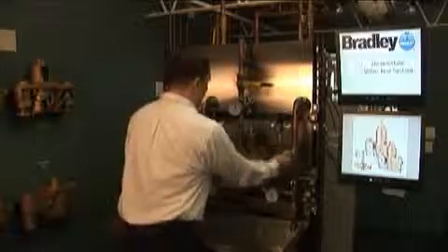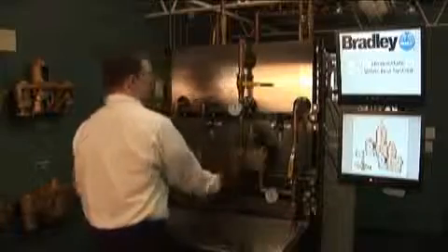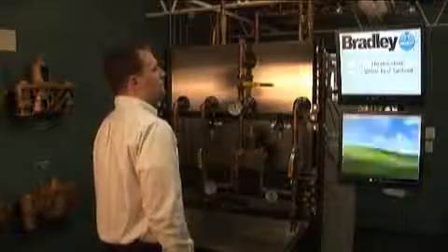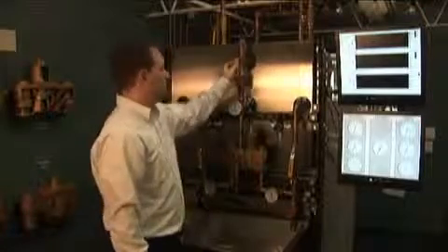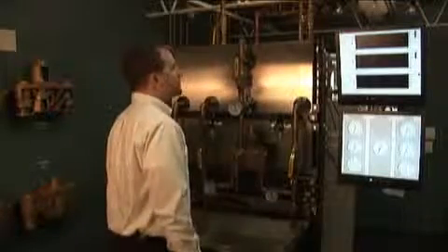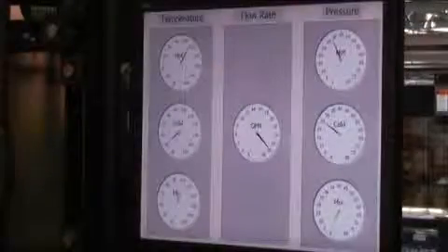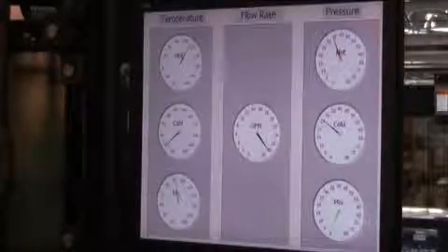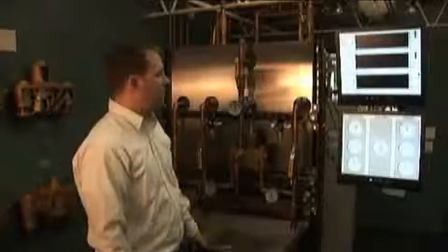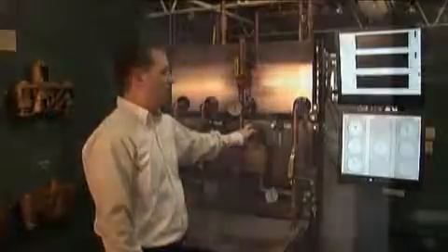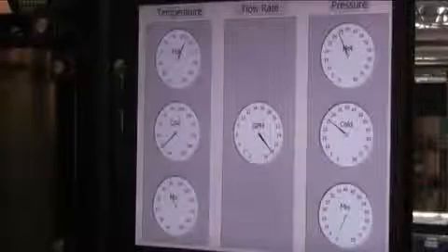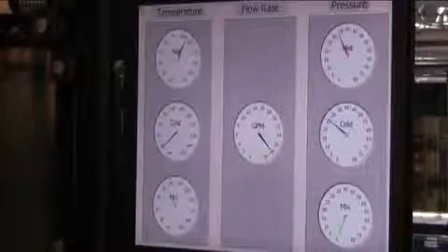I'm going to repressurize. And I will begin another test. Start the flow of water and let the instrumentation collect the data. You notice my mix temperature is lower in this case. Because I'm using an emergency mixing valve, we want a temperature that's lower than 90, 95 degrees. So this is set at about 85.